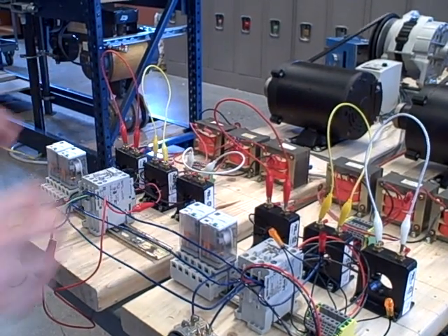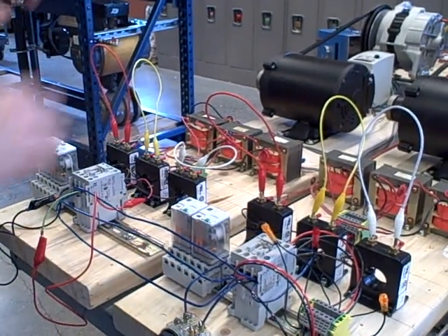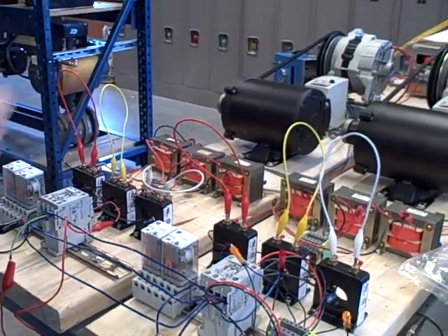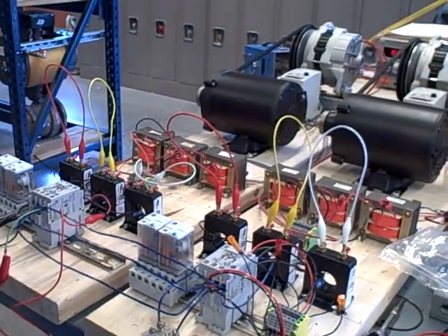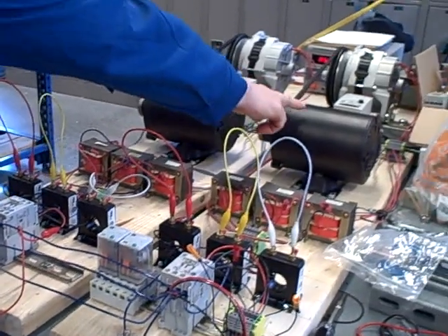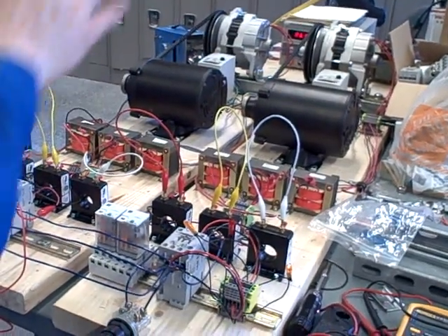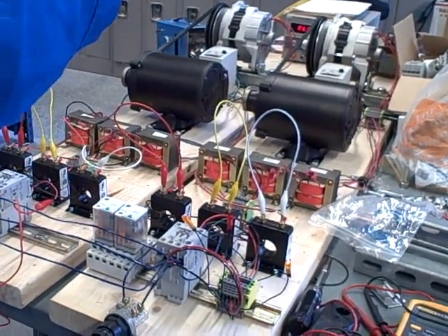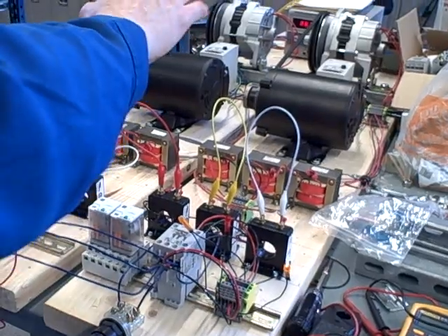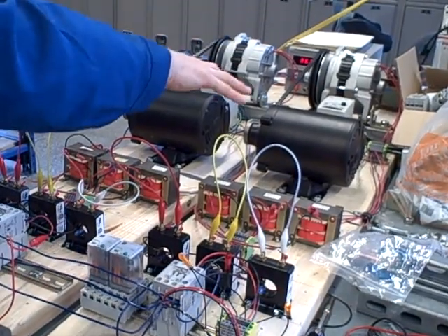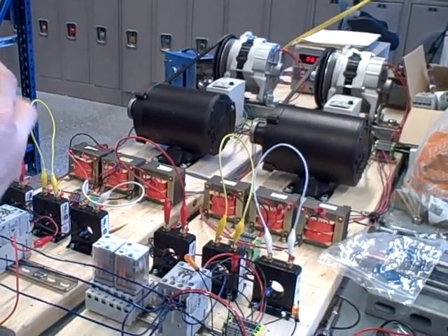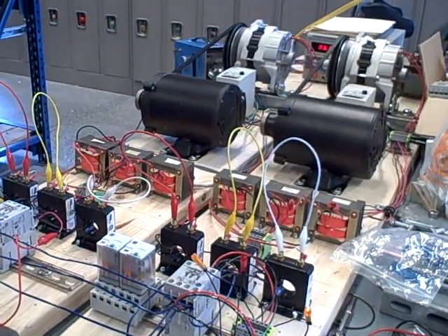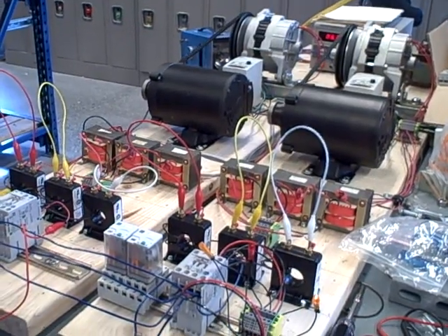So right now when we have them in sync, and we have these two induction motors powering them, the ability of the induction motors here to slip is what allows these two generators to actually stay in phase with each other, even though the motors would actually be having them spin slightly different speeds if left to their own devices.